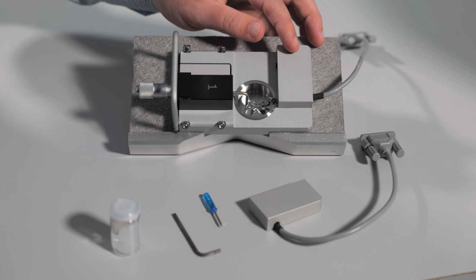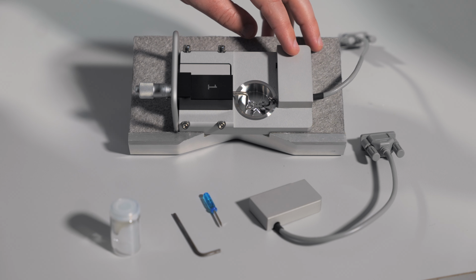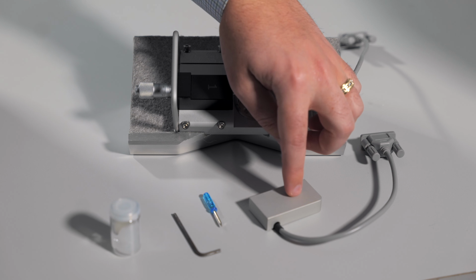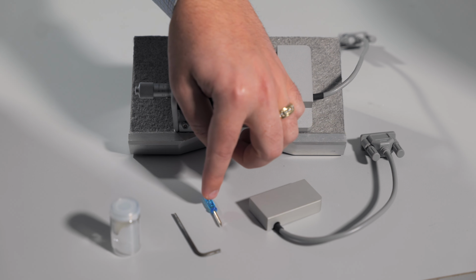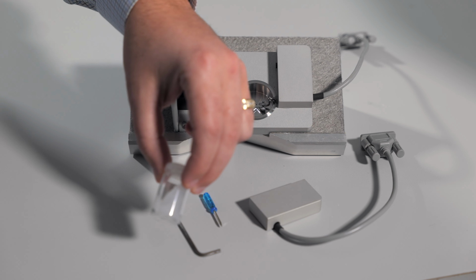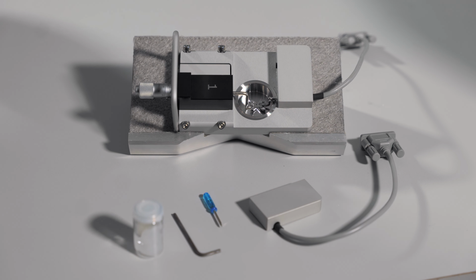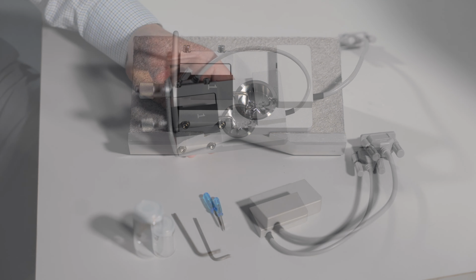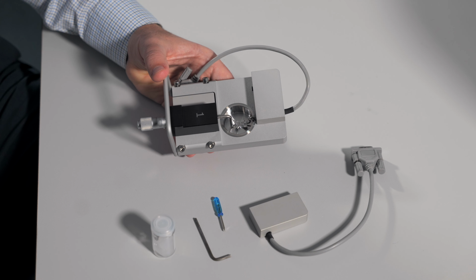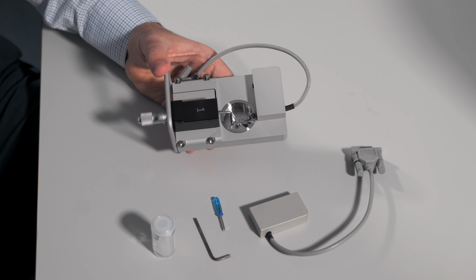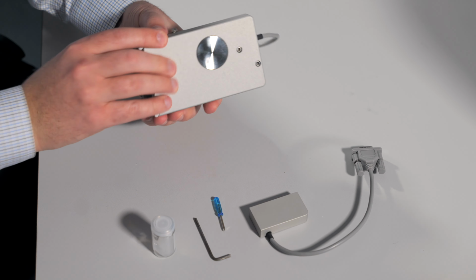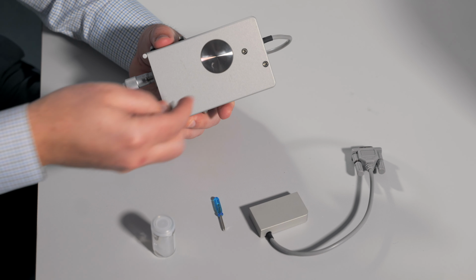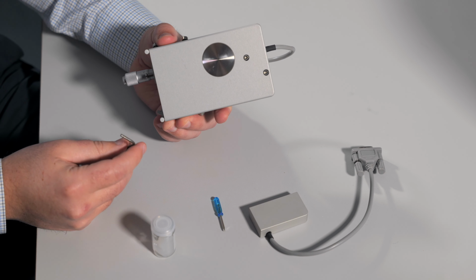In order to change an unresponsive transducer in the wire myograph chamber, you will need a replacement force transducer, the screwdriver, Allen key, and clear silicone-based grease that came with your system. The first thing you will need to do is remove the old transducer from the myograph chamber. Flip over the chamber and take your Allen key to loosen the 2 screws on the bottom of the chamber.